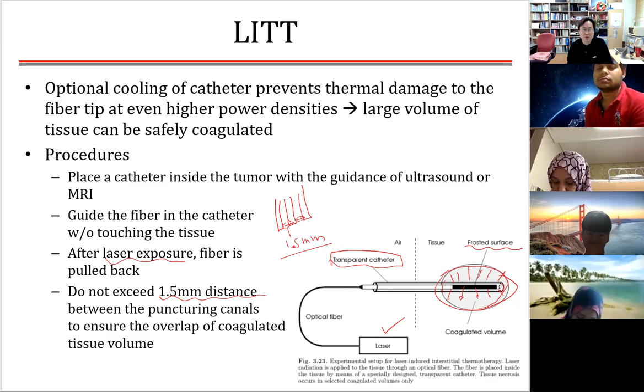When you are doing this, you can have multiple catheters, but do not exceed 1.5 millimeter distance between the puncturing canals. What they mean is that when you are using multiple optical fibers for treatment, between those catheters you need to have less than 1.5 millimeter separation. But I think this also depends on the properties of the tissue and the laser wavelength. You have seen this one already before.